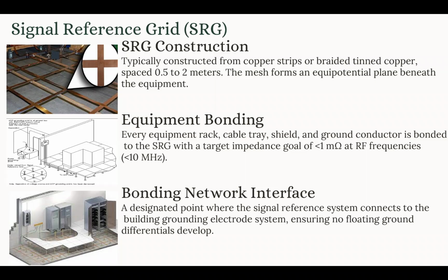Okay, now there are several recommendations when we talk about the IEEE 1100 about the SRG. One would be the construction, like material. It should be copper strips. The spacing between those strips should be between 0.5 meters to 2 meters. And the layout should be beneath or integrated into the equipment room floor, so the mesh must cover the entire area. Now we have an impedance target: we have to have less than 1 milliohm at RF frequencies.